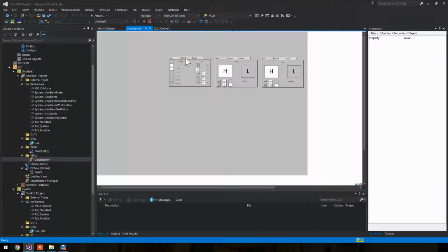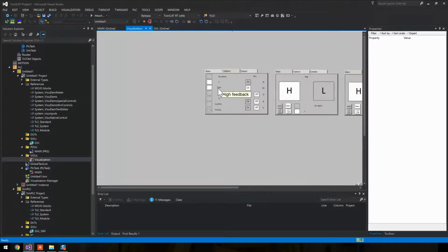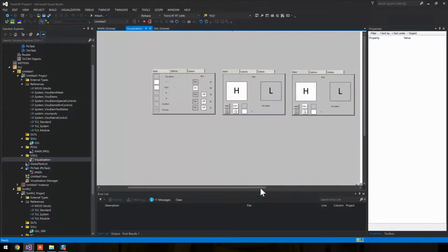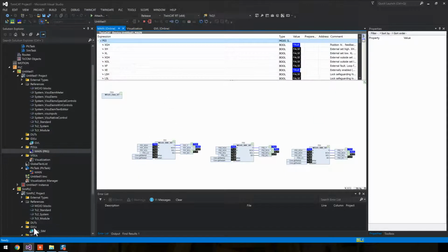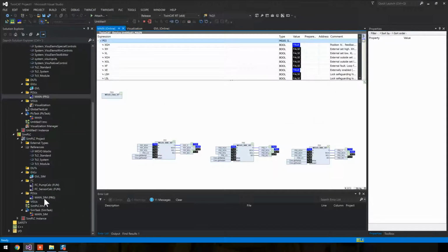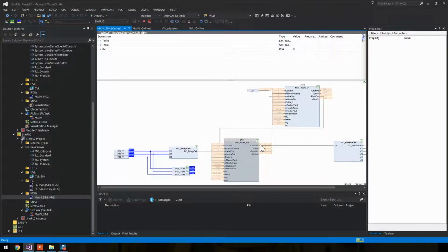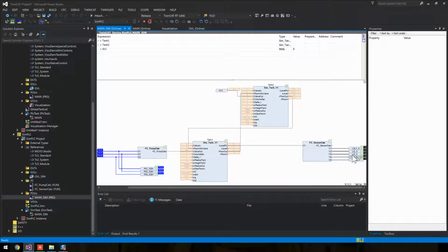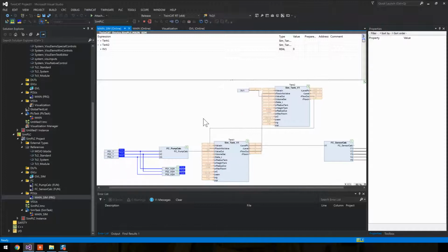Seems okay. In the options here we have the binary feedback. We turn it on, that's our command, turn on. And we received the feedback, and it worked. But what's going on now, we really have no clue. So we might be emptying the tank, and when the tank is empty, the pumps are pumping air, and pumping air is not a good idea. It's probably going to ruin the pumps. Let's see what's going on here. Yeah, we're pumping air. It's empty.